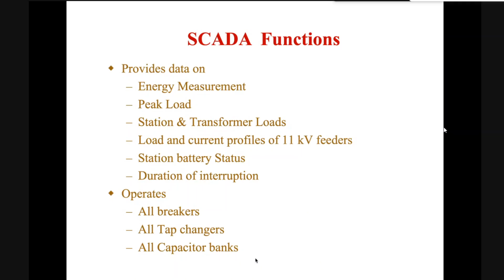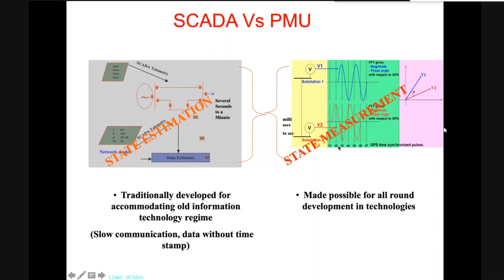You know the importance of operating OLTC, on-load tap changer, and the importance of operating the capacitor banks remotely. Depending on the requirement of the power factor, we can remotely switch on and switch off the capacitor bank, even though we have APFC, automatic power factor correction, everywhere. But we can also operate it with the help of SCADA. The problem with SCADA is that it will just estimate the value, but PMU can measure it. If you see here, the input requirements of the PMU, it may look like a conventional meter.